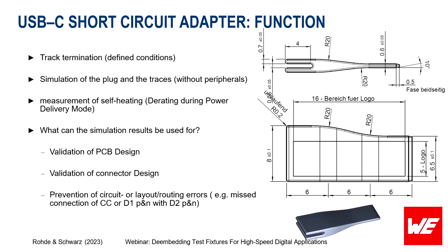That means that you can insert this short circuit adapter into a plug or receptacle and you have a defined end position. So you can measure all lines by themselves. With these simulation results, without any peripheral devices, cables and so on, you have only the product itself tested.